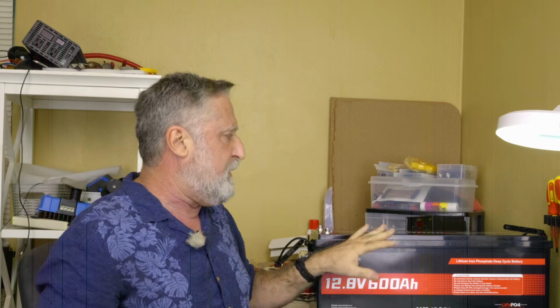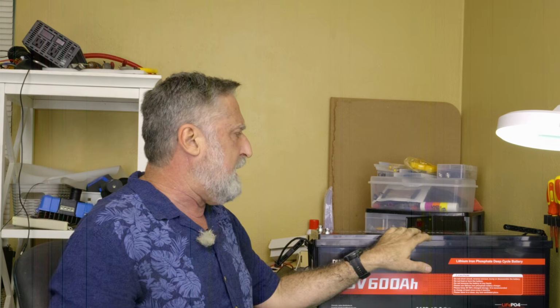That would be cool, it has a 200 amp BMS. That means it can't put out more than 200 amps at a time. If you ask for a 210 amp load, like a big inverter, it's going to puke and the BMS is going to shut down and overheat. Along those lines, they say don't charge it over 100 amps, they say 50 to 100 amps. Now the cell should be able to take 300 amps, so that's a BMS limitation.